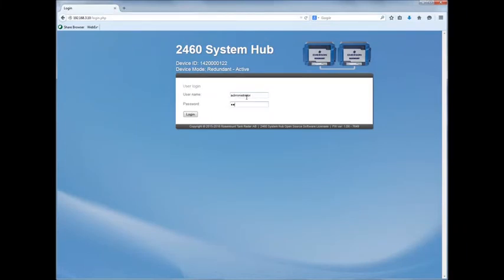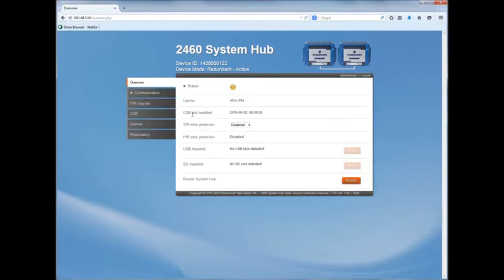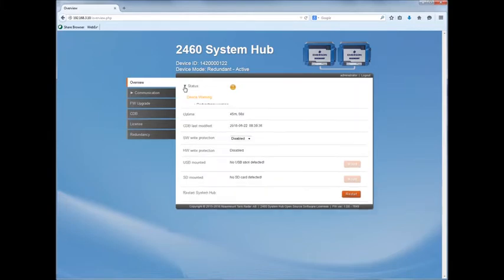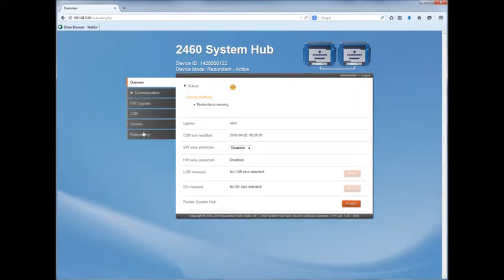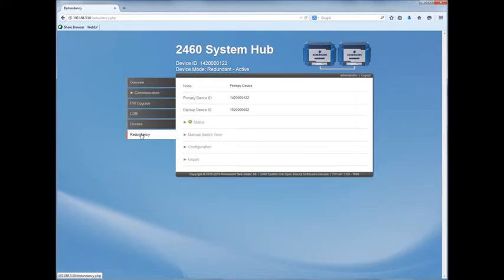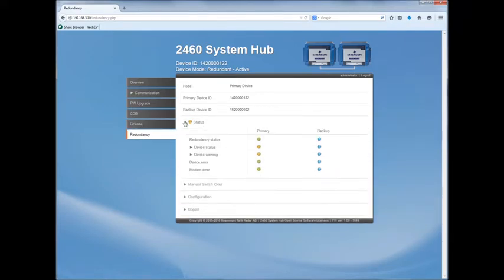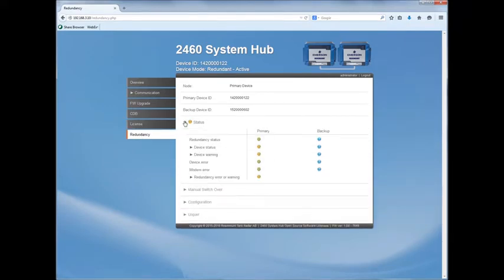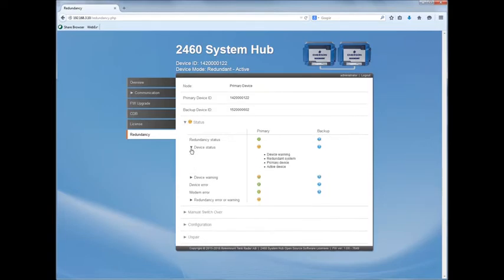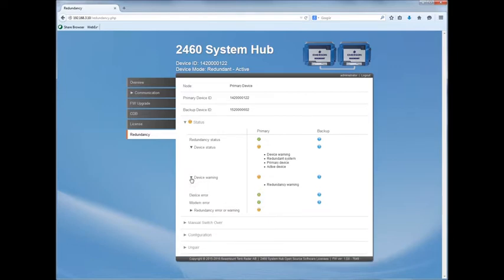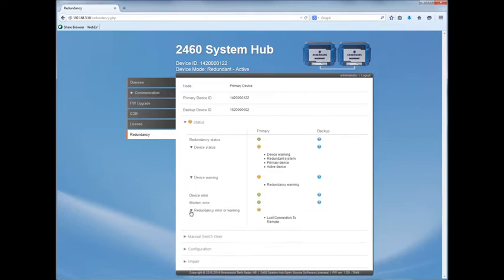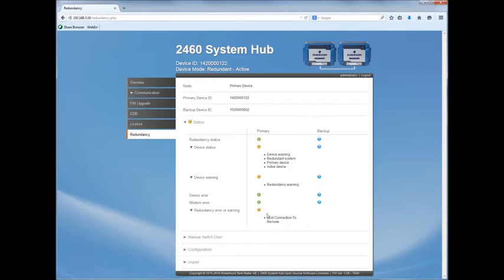We log on to the unit and we go to the Redundancy tab. We can see that there is a warning and there is unknown status for the backup, meaning that we have lost the unit. We can also see it says lost connection to remote, so we don't have any communication with the backup unit.